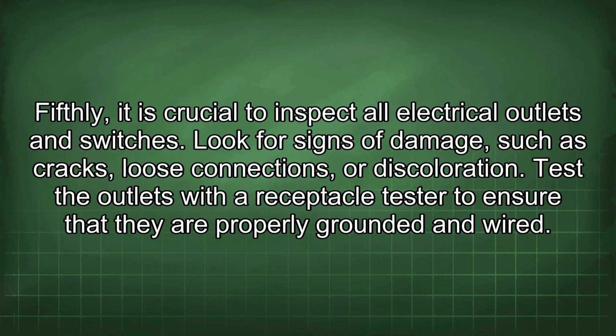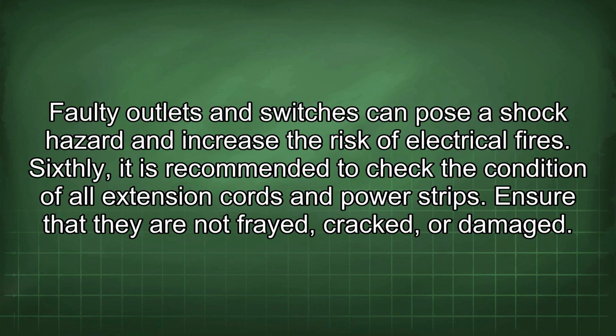Fifthly, it is crucial to inspect all electrical outlets and switches. Look for signs of damage, such as cracks, loose connections, or discoloration. Test the outlets with a receptacle tester to ensure that they are properly grounded and wired. Faulty outlets and switches can pose a shock hazard and increase the risk of electrical fires.